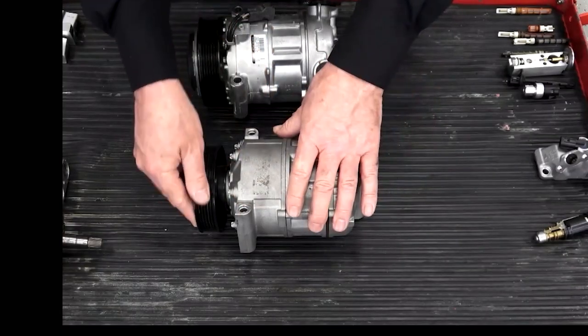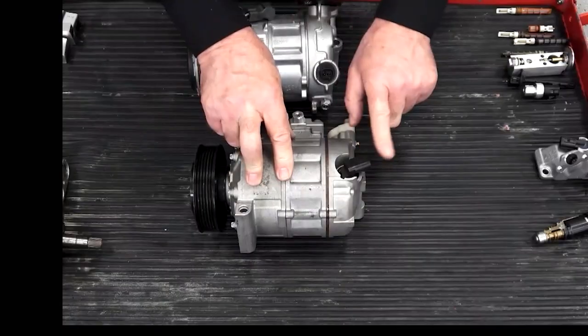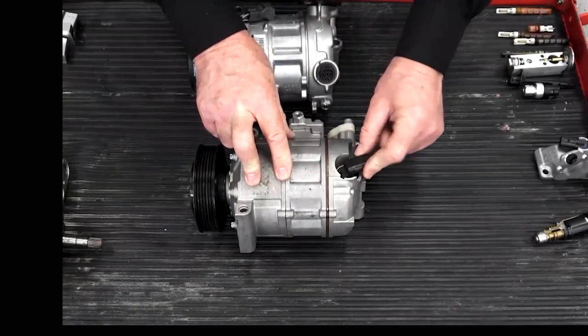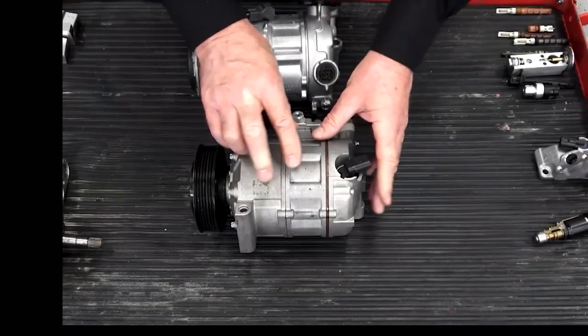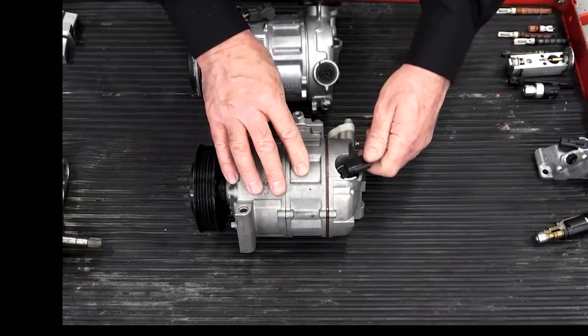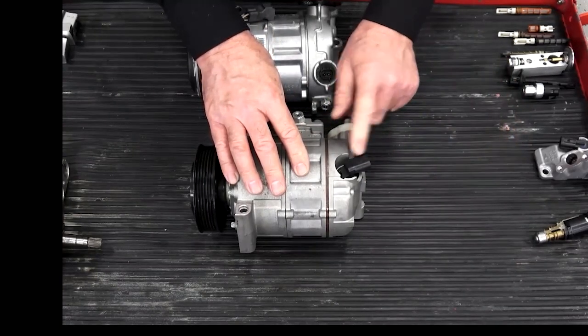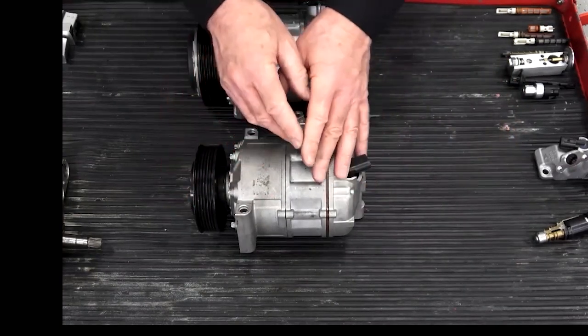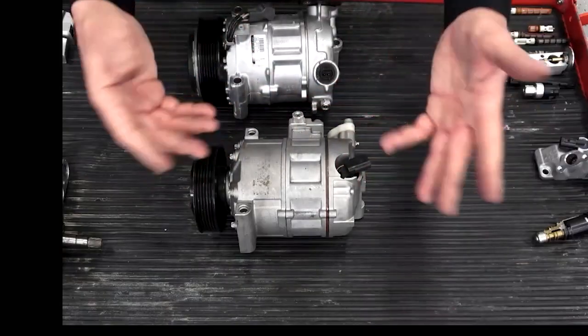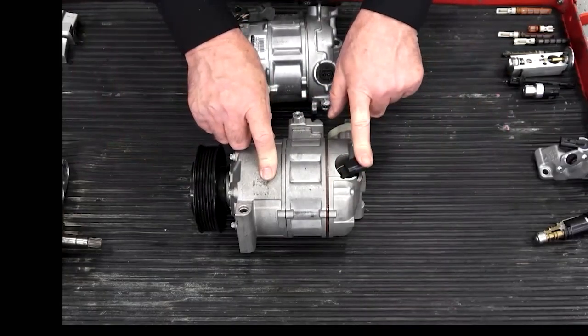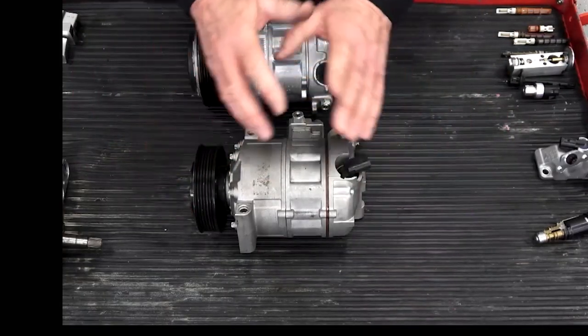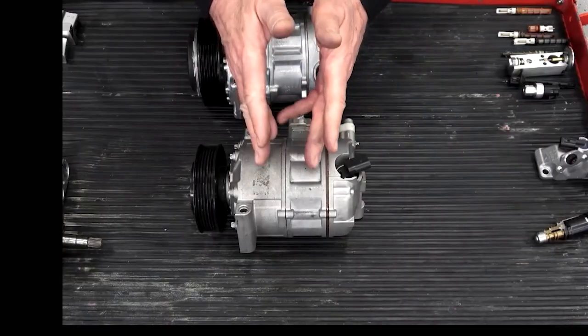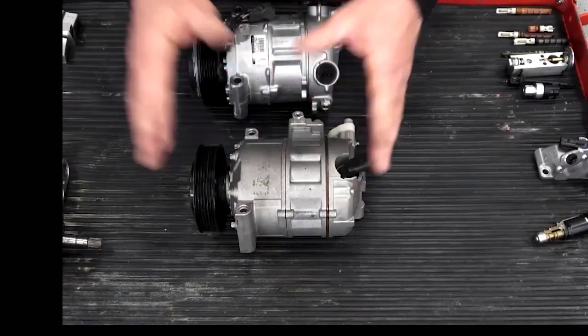So if it's 40 below, if it's very cold out, I don't need air conditioning, the computer simply won't send a command to the solenoid here. And in fact, if you unplug the electrical connector from the solenoid, that will default if you were looking at your gauges and the compressor was working. If you unplug that solenoid on any of these compressors, the compressor is going to default to minimum displacement, and it's going to go down.